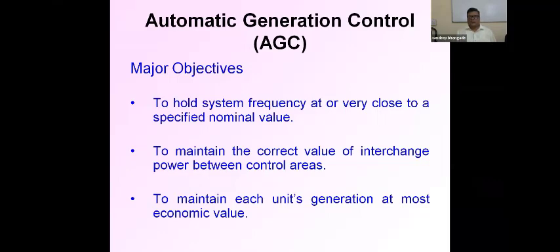Second is to maintain the correct value of interchange power between the control areas. It means if there is some deficiency in one control area and another control area has some surplus power, the power flows from the control area where the power is surplus and is given to the control area where there is a deficiency in the power. So when this condition arises, the AGC maintains the power flow from one control area to another so that the system frequency should not deviate. Okay. Another is to maintain each unit's generation at the most economic value. So these are the major objectives of automatic generation control.